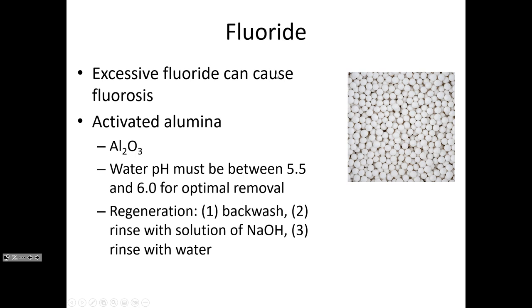Activated alumina for fluoride removal is very similar to ion exchange, where the filter media has a preferential absorptive capacity for what you're trying to remove. Rather than a packed column, you could use large beds of activated alumina similar to sand beds. It's a pH-dependent process — to remove fluoride, the water pH must be reduced to the range of 5.5 to 6. The depth of the column depends on how much fluoride you're trying to remove.